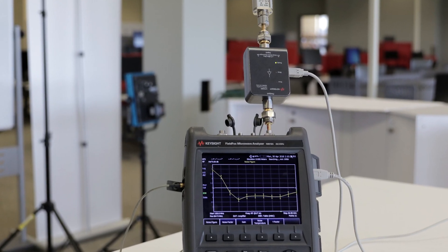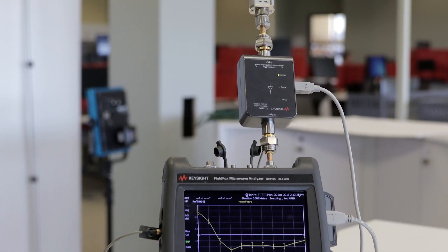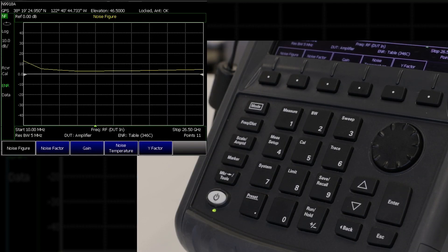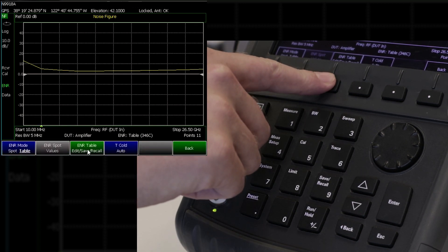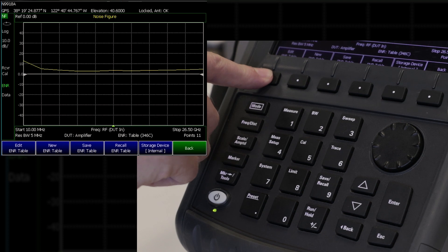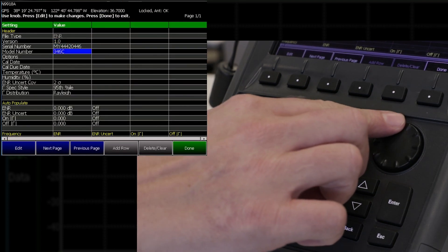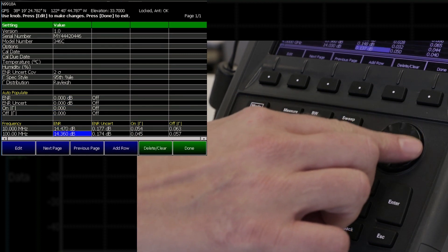For improved accuracy, we also recommend using the external USB pre-amplifier. The first step for your noise figure measurement is to set up your noise source ENR table. The output of a noise source is usually given in terms of excess noise ratio, or ENR. This must be known for accurate noise figure measurements. Any uncertainty in ENR transfers into uncertainty of the measured noise figure, dB for dB. Each noise source comes with its own ENR, uncertainty, magnitude, reflection, noise source on and noise source off versus frequency. I have entered these values for the 346C noise source.